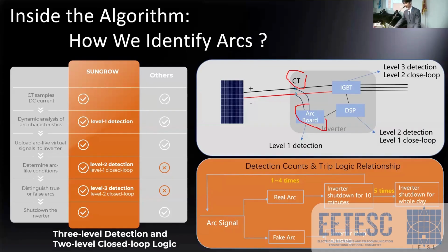The arc board will do the analysis or the matching. Then there is a DSP, which is the brain of the board. IGBT is the core component of the inverter. So how does the 3-level detection work? Like this: the CT captures the arc fault signals and then forwards them to the arc board. On the arc board, we have a local database on the data flash. So the CT forwards the signals to the arc board to match, no matter the results.